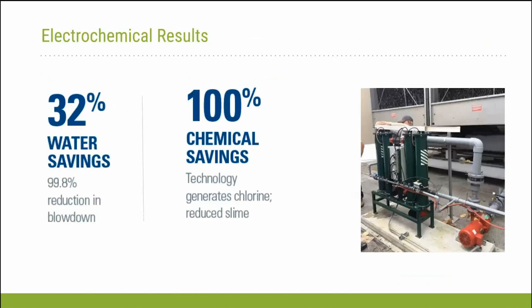Next slide. Basically, the results of the testing was that we saw a 32% water savings from the system, and that was a result of a 99.8% reduction in blowdown. When this system started up, we changed conductivity settings to try to increase cycles of concentration, but for very long periods of time the blowdown system really just turned off, and the solids and the scale were being pulled out of the system by the electrolysis system. And again, we had 100% chemical savings; we turned off all of the chemical scale inhibitors. But when we assessed the system, we did before and after examinations and pictures, to make sure that by removing those chemical additions we didn't do any damage to the system.